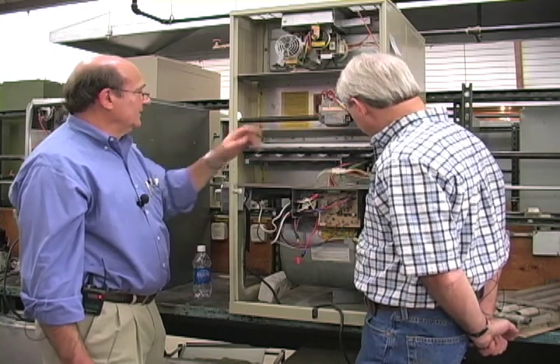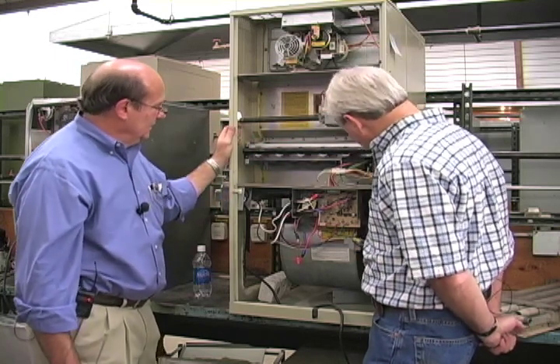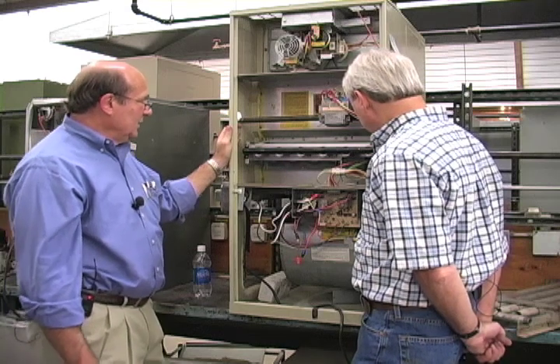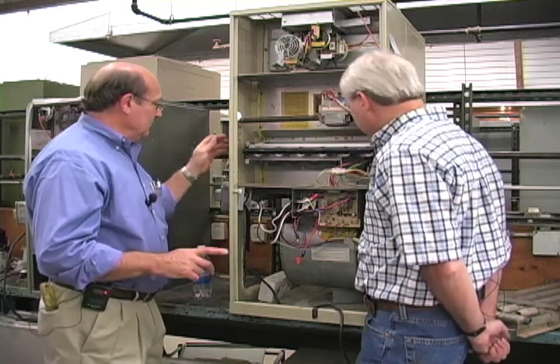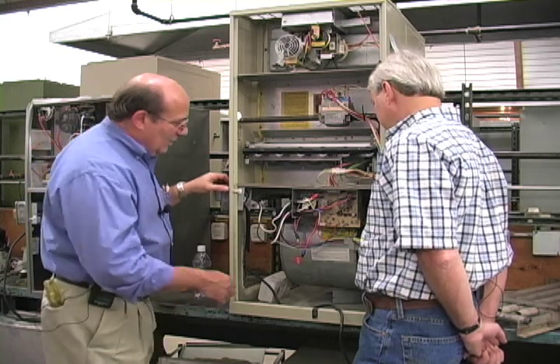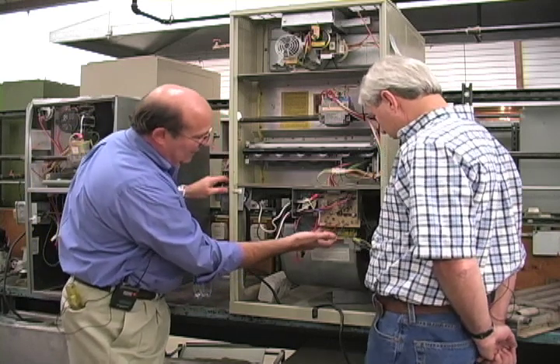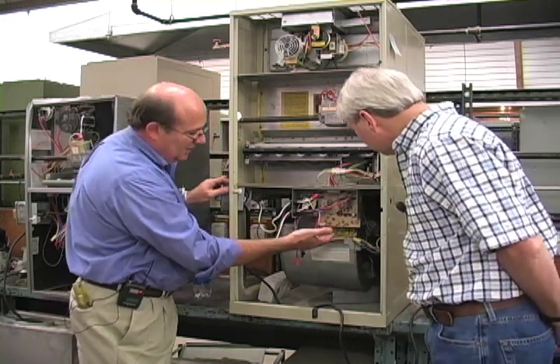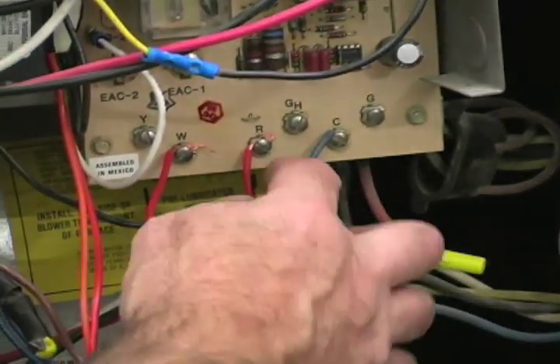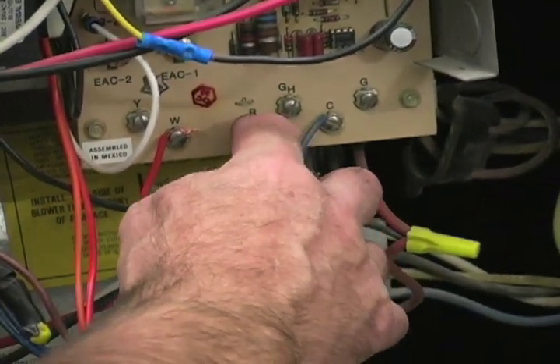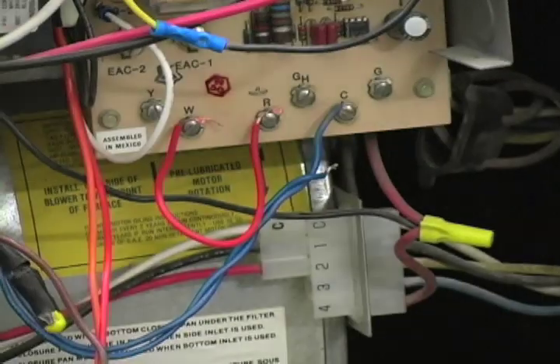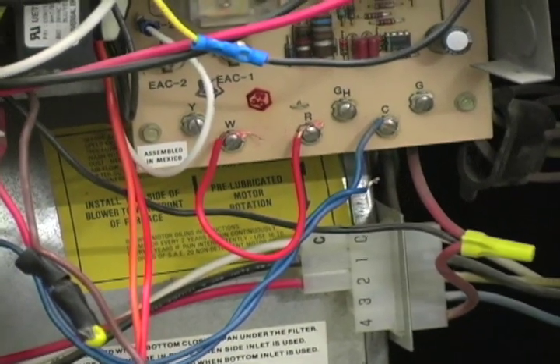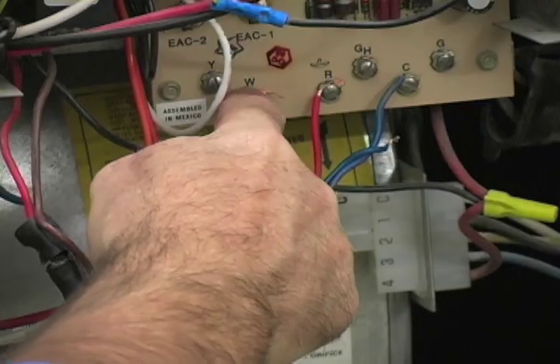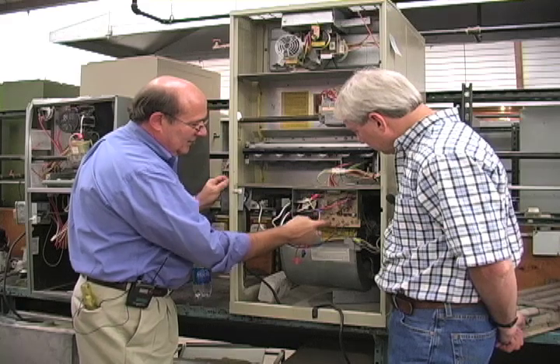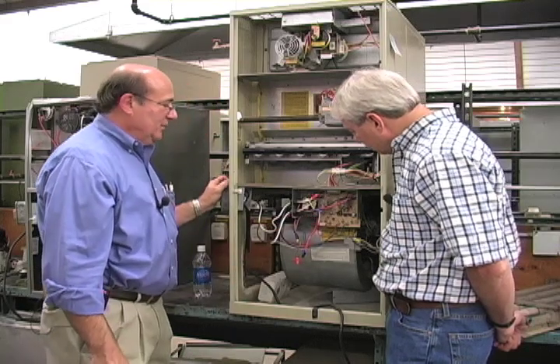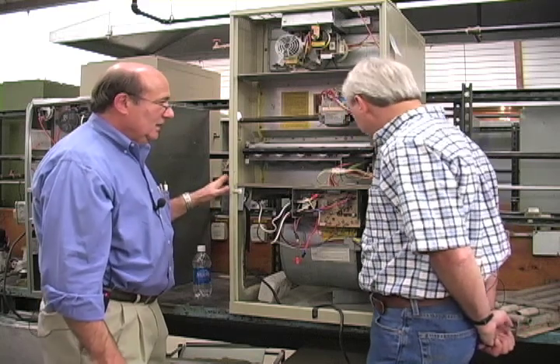And I'm sorry that I can't provide that vision for you today. I want to show you one other safety feature, but let's try and run this through the cycle first. What I had to do in this case was just put a jumper on here because this furnace isn't ready to go. So I jumped out where the thermostat would normally be. The red lead comes off of here, and that's power from our thermostat, goes up to our thermostat in our house. The thermostat switch makes and brings power back down to the W terminal on the circuit board, which is going to bring our primary call for heat.